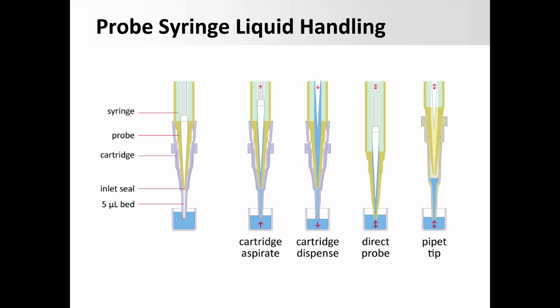This syringe is mounted on 9 mm centers in a more or less standard liquid handling head, and the cartridge connects to it by an inlet seal forming a connection with the tip of the probe that's connected to the syringe. That inlet seal functions like a miniature luer fitting. Because it's so small, it can hold pressures of several hundred psi, even though only a couple of pounds of force are required to insert or remove the cartridge from the device, which is well within the range of any robotic system. So this now provides a means, by moving the syringe plunger in a precise way, that any pipetting system is able to do.